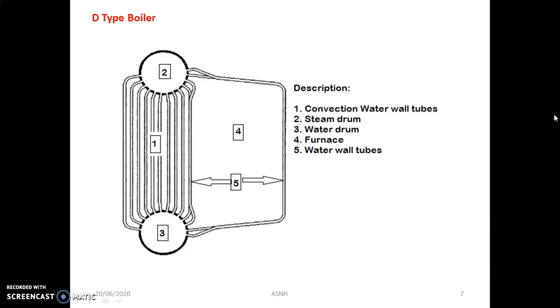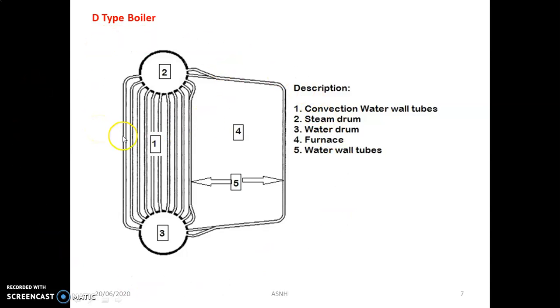Another type of water tube boiler is the D-type boiler, mainly used in sugar factories and process and food processing industries. The pressure capacity is in the range of more than 40 bar up to 60 bar. The name is given because it looks like the letter D shape. It consists of five important components. The first is the convection water wall tubes — in these tubes water is continuously circulating and the rest portion gets surrounded by fire.